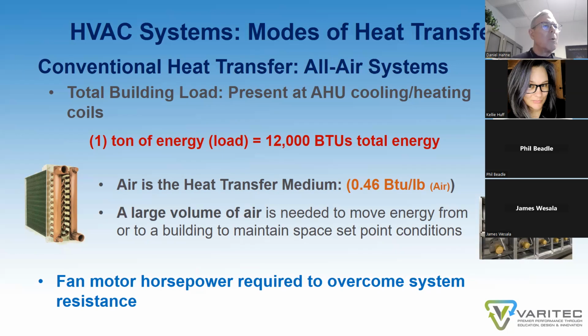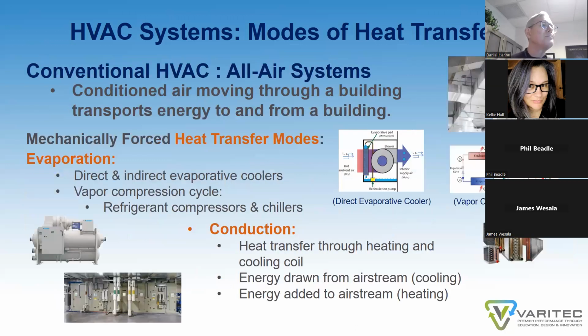Or in heating mode, we warm the supply air temperature up to a degree that we add the heat to the building that was lost due to the cold outdoor environment. The problem is that if air is used as the heat transfer medium, air is not very dense, so it can only hold 0.46 BTUs of energy per pound of air. So in order to move heat or add heat to a building, you need to move a lot of air. Consequently, you have to use fan horsepower to do that. Conventional all-air systems then condition a building by moving air throughout the building. And the two modes of heat transfer that apply are mechanically forced.